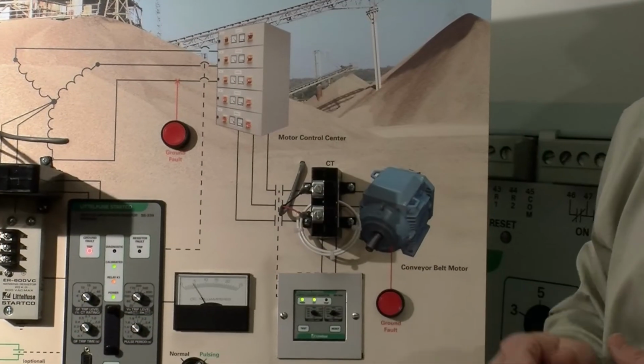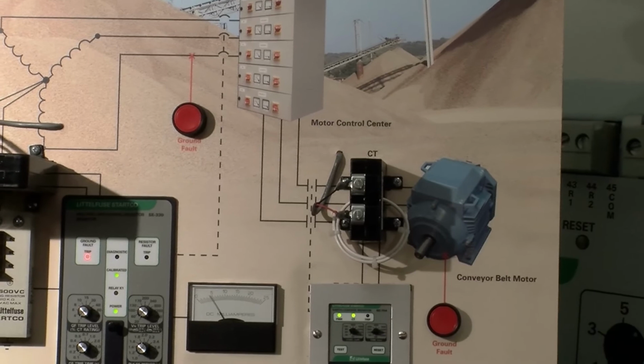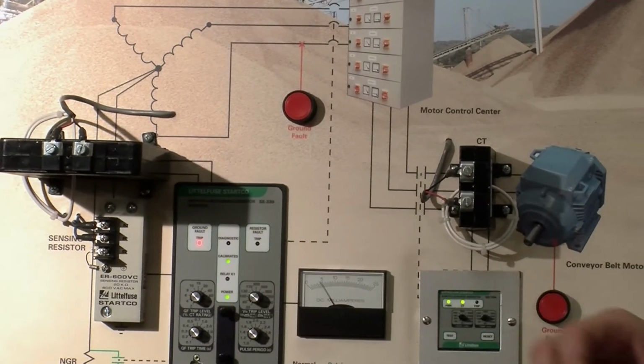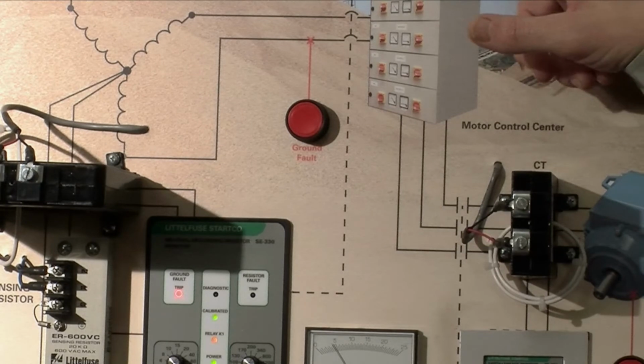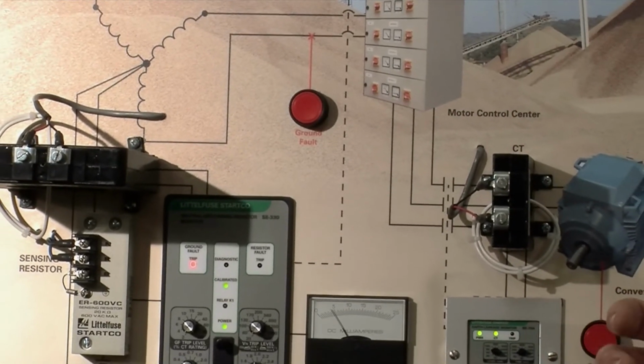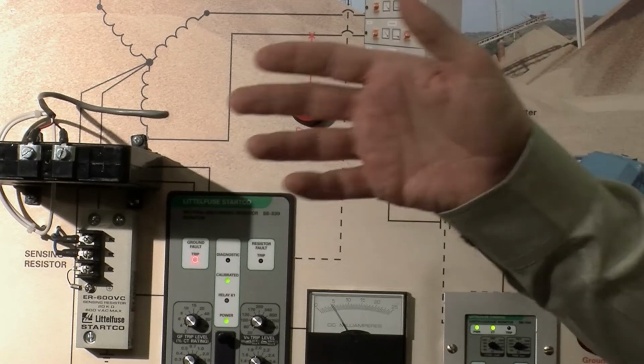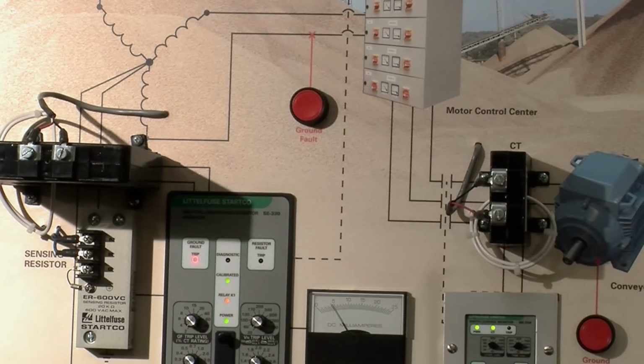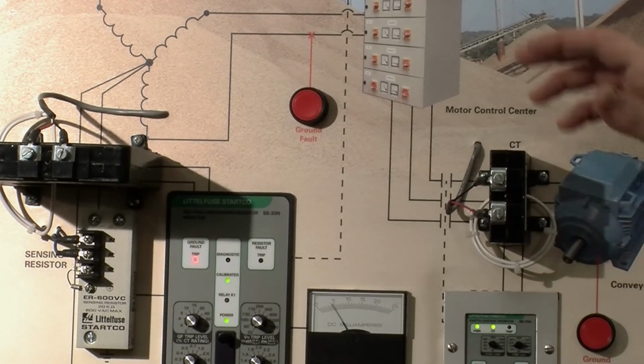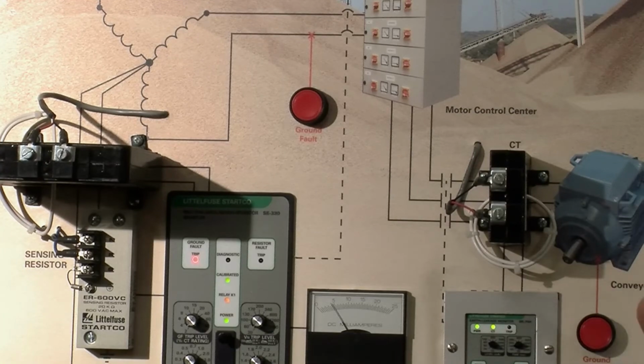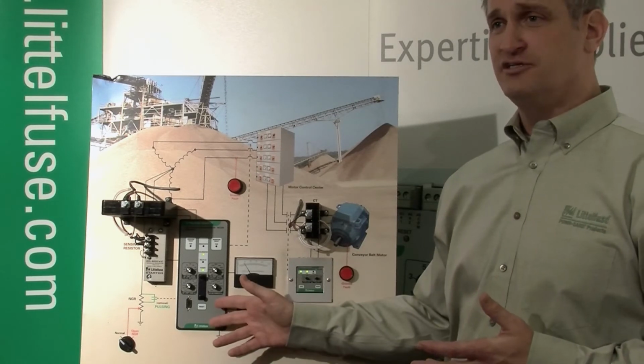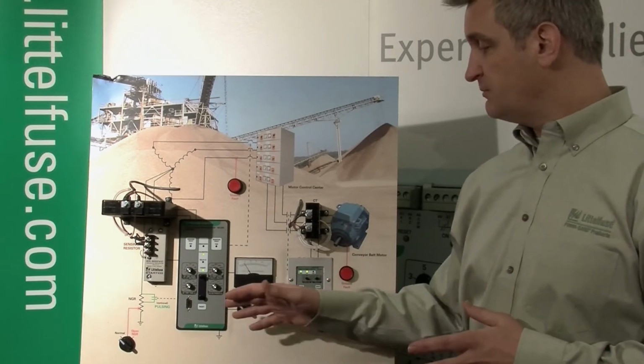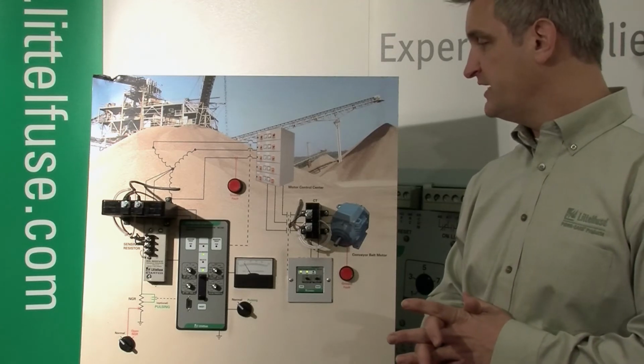For safety reasons, people are putting the SE701 in each of their feeders in the main switchgear. The main benefit is that the electrician says, yep, I know there's a ground fault, I acknowledge it, I see it. I'm going to look at all my 701s in my main switchgear to find out which one has a ground fault. The electrician starts out downstream of that to find the ground fault. So it expedites the troubleshooting process, but there's also a safety aspect to it. It keeps the maintenance person out of the main switchgear, where the arc flash hazards are the highest. We actually pioneered this technology about 25 years ago. We're the first ones to come up with this idea, and we've really come a long way since then.